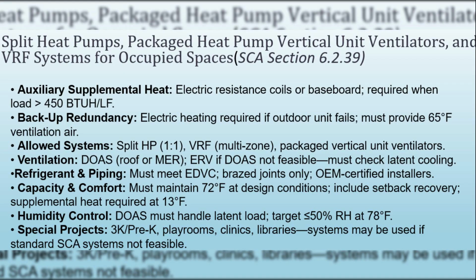Then we have backup redundancy heating. This is protection for when the outdoor unit fails entirely, like from a refrigerant leak or compressor issue. In that case, electric heating must step in to keep the space warm, ensuring at least 65 degrees Fahrenheit tempered ventilation air. The acceptable system types for occupied spaces are 1-to-1 split heat pumps, VRF systems with multiple indoor units tied to one outdoor unit, and packaged vertical unit ventilator heat pumps that use outdoor air through a wall louver. DOAS units may be roof-mounted or located inside a mechanical room, depending on space, roof use, and aesthetics.